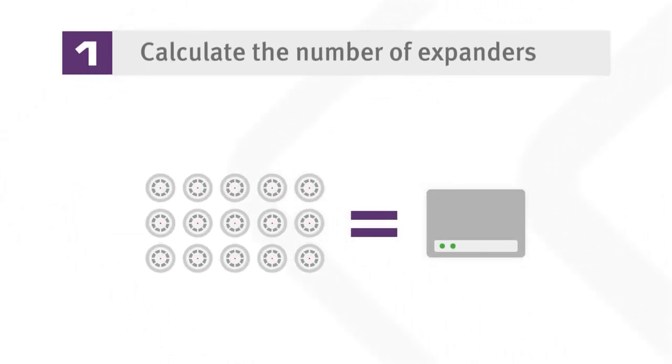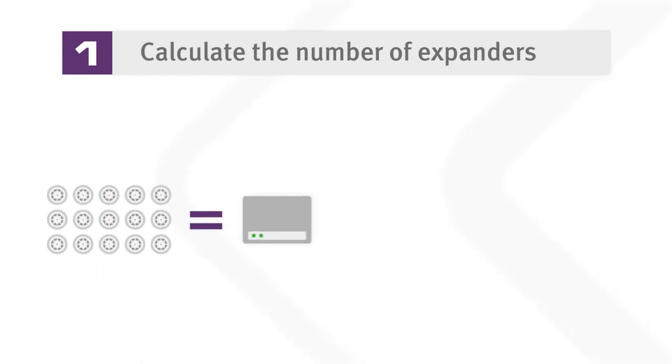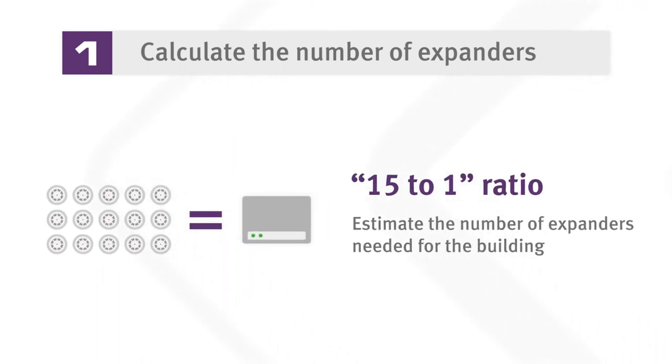On average, the system needs one expander for every 15 sensors. You can use this ratio to get a quick estimate of the number of expanders needed for the building.